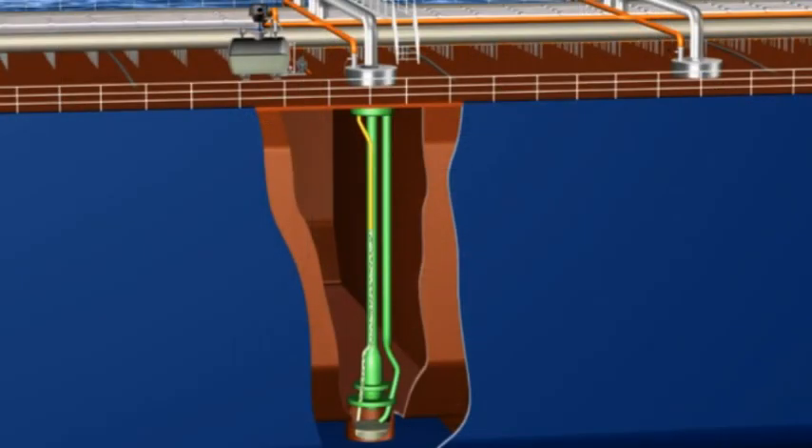Because of the large airflow, the liquid can easily be lifted 25 to 30 meters in vertical direction. Experience shows that one AB950EX can transport liquid over a distance of up to 70 meters in total.